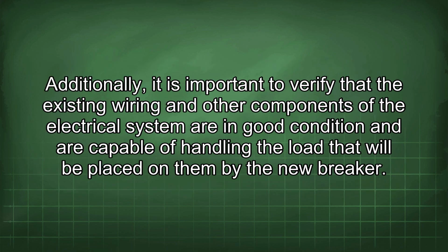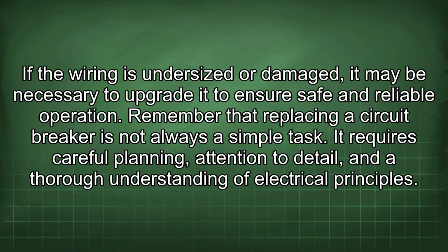Additionally, it is important to verify that the existing wiring and other components of the electrical system are in good condition and are capable of handling the load that will be placed on them by the new breaker. If the wiring is undersized or damaged, it may be necessary to upgrade it to ensure safe and reliable operation.